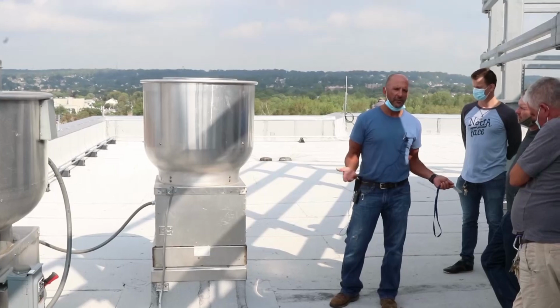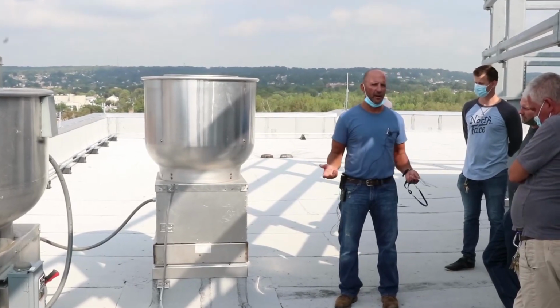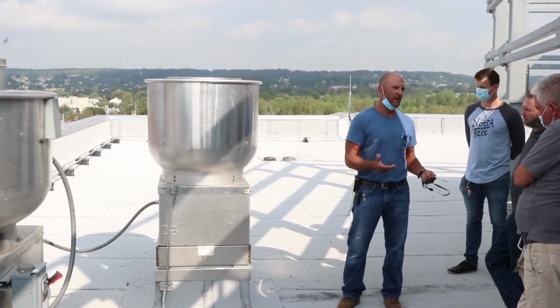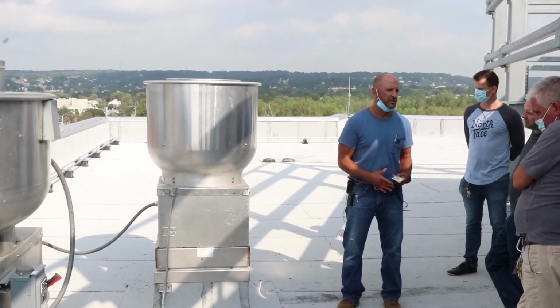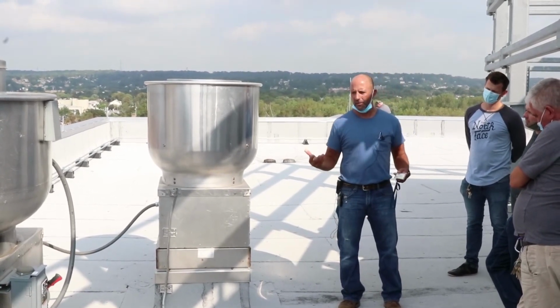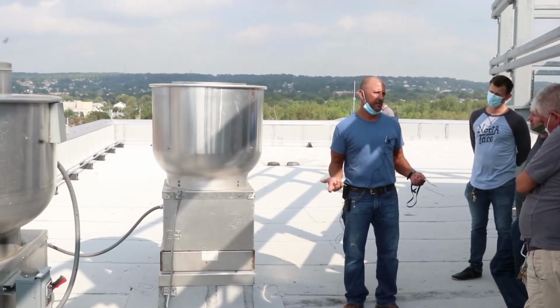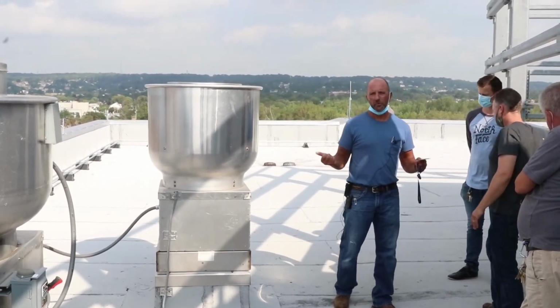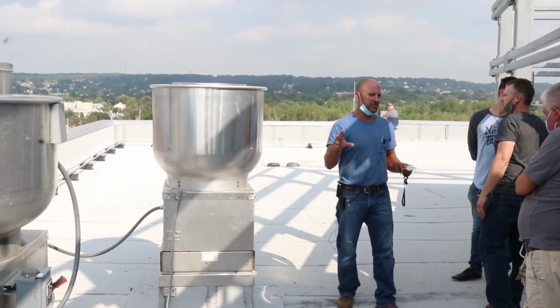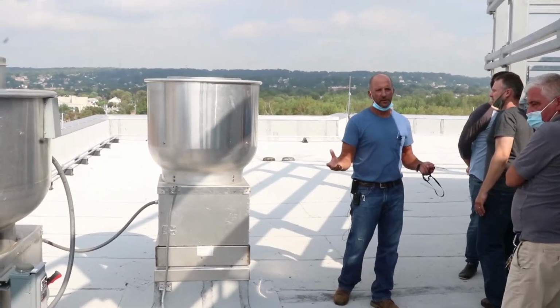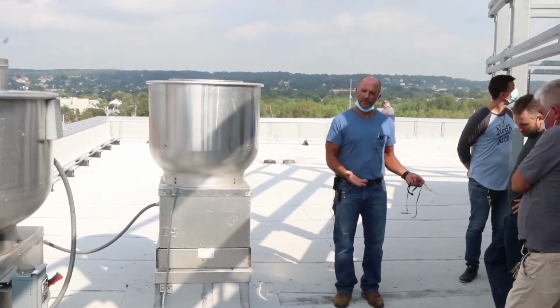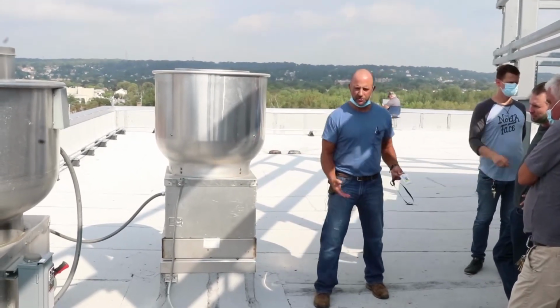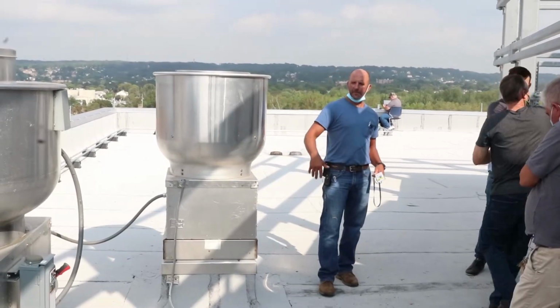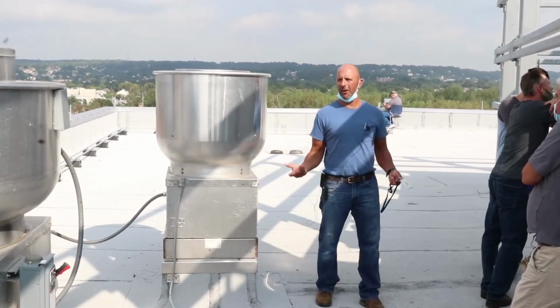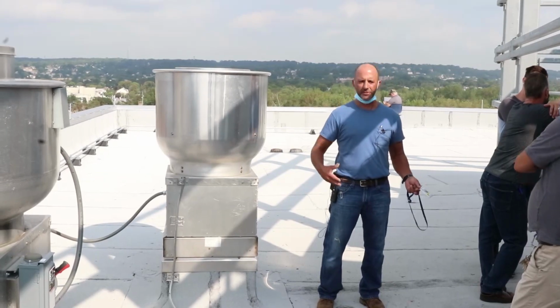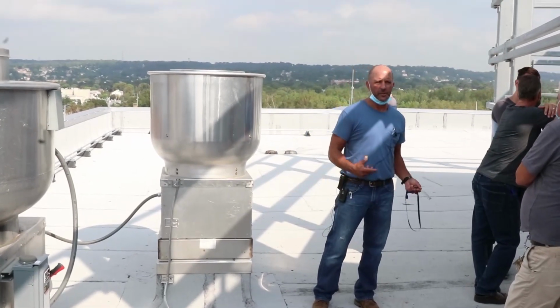You'd have to go to the drive and see what's going on with the drive. Was it commanded on? We can take a look at that on the 5th floor where the drives are. Was it commanded on by Johnson? What speed was it set at? All those speeds the drives are set at were set by the balancer. After he measured them, we put a speed in, and he's going to send the command to start it and put in a speed command. If you get a fault, it'd be at the drive. If you were to turn one of these drives off, just for your own knowledge, and you go to turn it back on, it might not restart because you might get a fault at the drive, since the drive doesn't see a load. So you might have to go down and reset the drive.